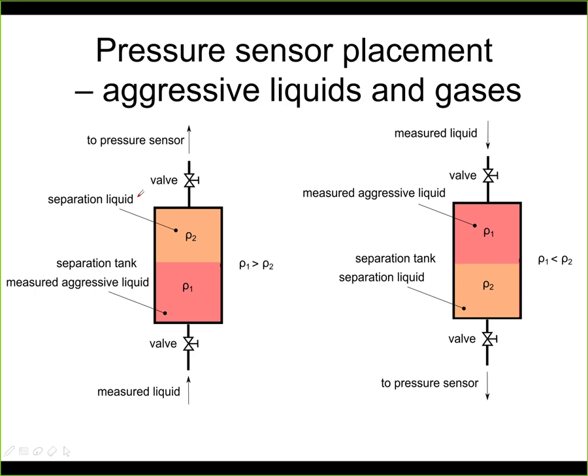So the separation liquid is some liquid that fills the entire system of the instrument from this separation tank to the sensor, and it's not aggressive. And in this case, it's in direct contact with the aggressive liquid, but since they do not mix together, we don't need to put any diaphragm. If they mix together, what you need to do is you simply install a diaphragm in here, and then this diaphragm changes the shape, goes like this or goes like that, based on the changes of actual pressure in the measured liquid. Now in this case, the assumption is that the density of the measured liquid is always higher, so it stays in the bottom. So here is the probe where you measure, where you tap your pipe of the liquid, and the pressure sensor needs to be always above, so that this whole system is filled at all times with the separation liquid.